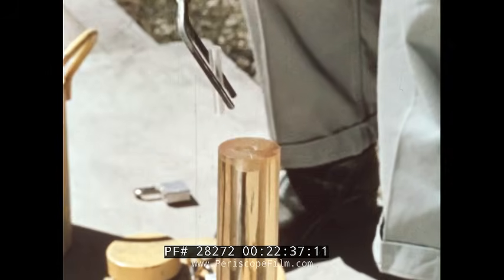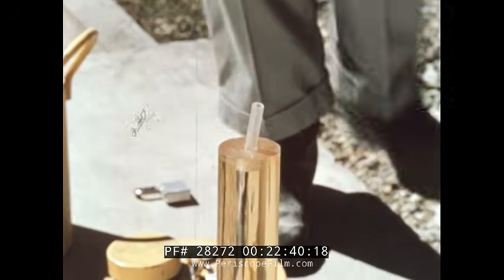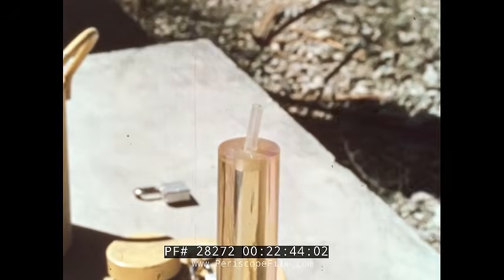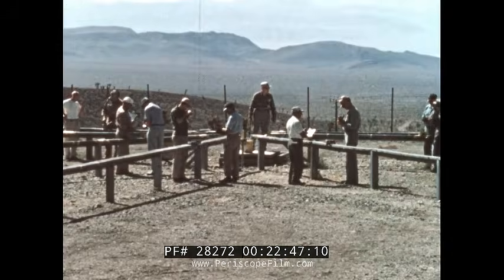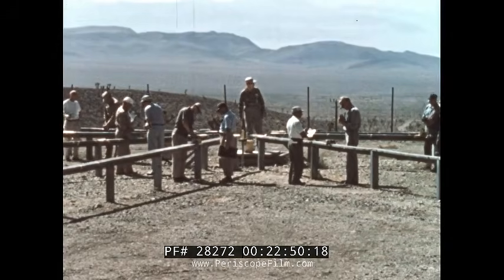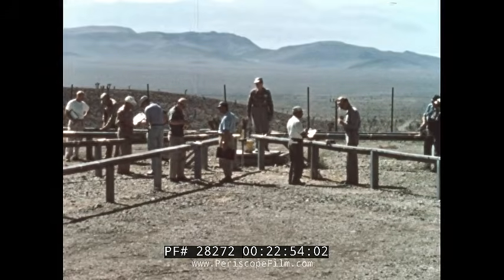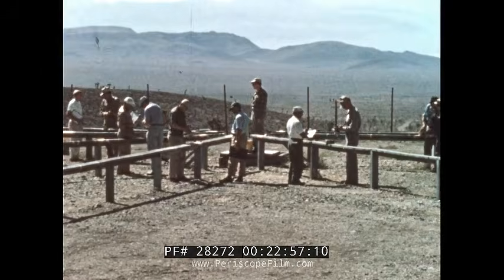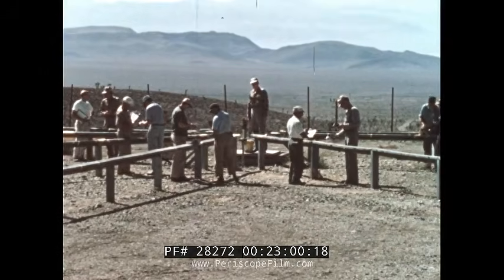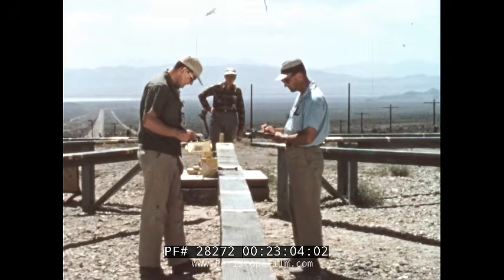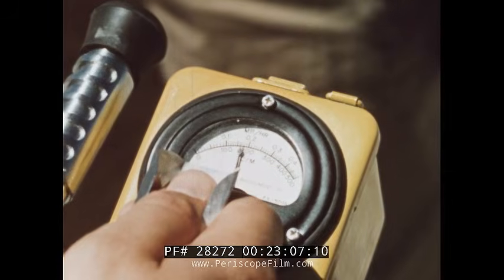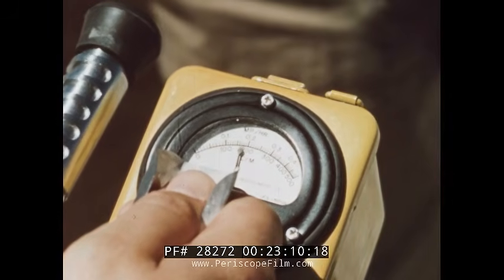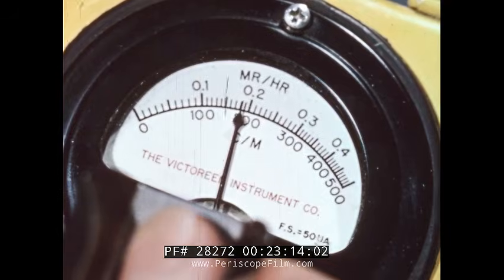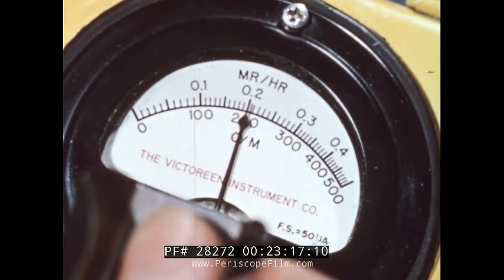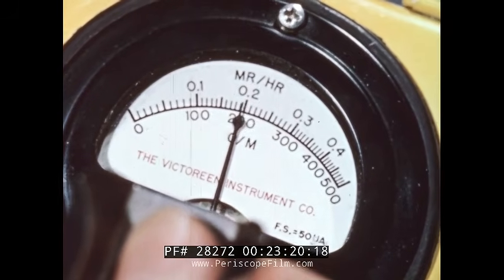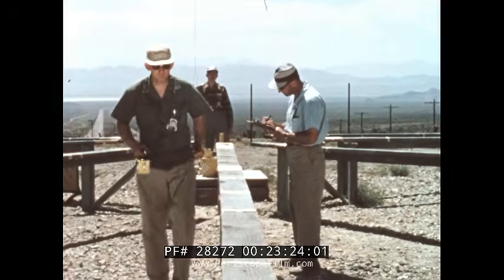Here, a relatively small 30 millicurie cobalt-60 source is being employed. Extending from the source stand are 7 wooden legs. Measured distances from 1 to 20 yards are marked on these legs, taking into consideration the known strength of the source. The monitors select one of these points at which the dose rate in milliroentgens per hour has been calculated. With the probe held carefully over the mark, the intensity reading is noted and recorded. Using this source at 5 yards, the V700 should indicate 1.9 milliroentgens per hour. If it does not, the scale reading is again corrected by rotation of the calibration screw.